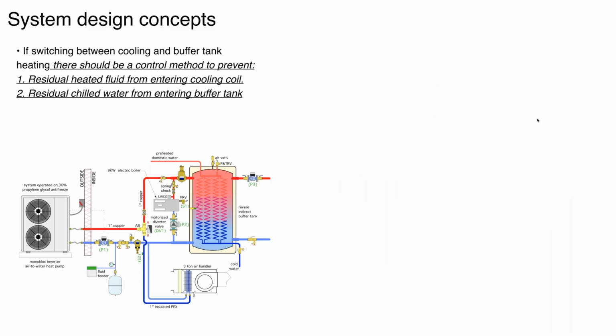All right, now let's talk about this. Here's that same schematic. Now, one of the little nuances of switching between cooling and, let's say, domestic hot water heating, when we shut off in domestic water heating mode and we resume cooling, you want to think about the fluid that's in the heat pump as well as in the piping from the heat pump into the mechanical room. That fluid could be 120, 130 degrees, depending on what that tank temperature was.